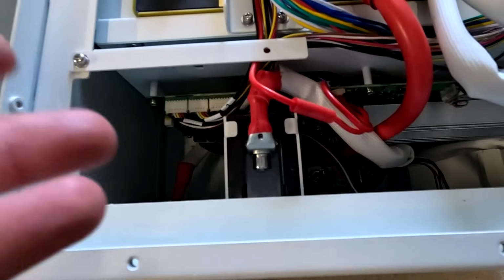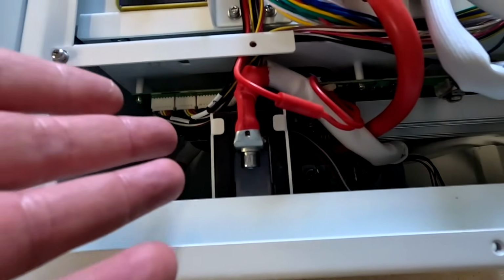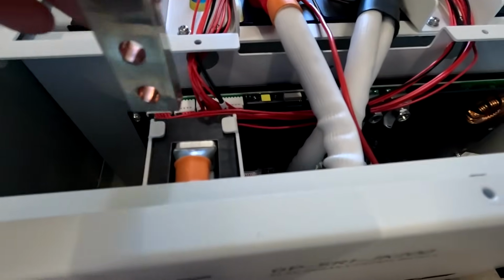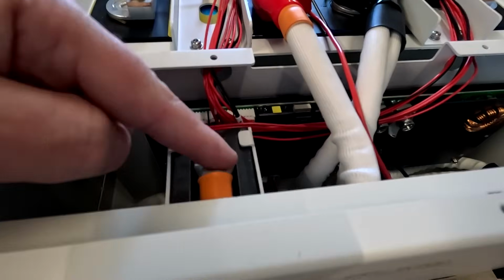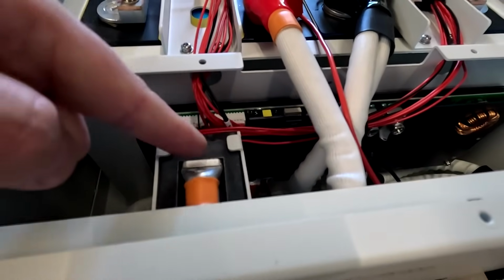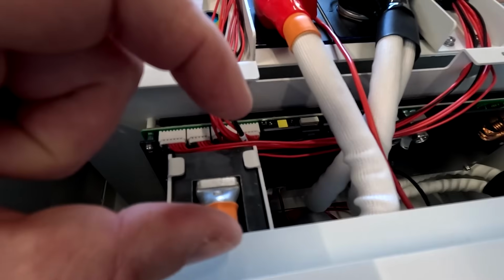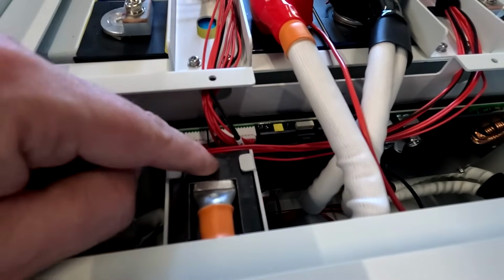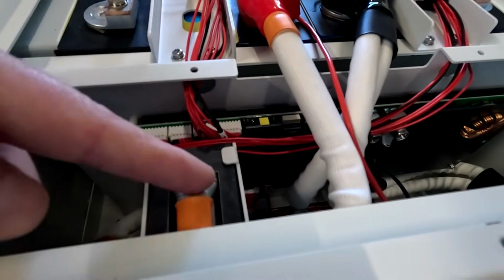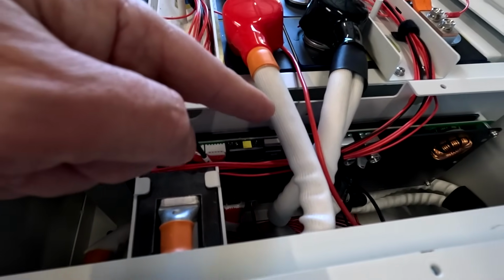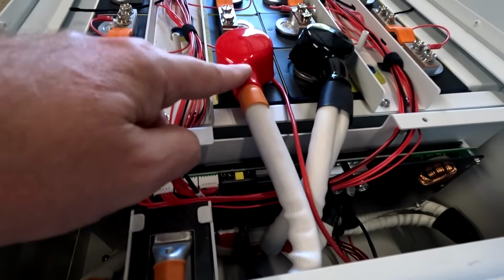But these ones here, I mean, we've got options, right? For example, you could have a piece of copper sticking here connected to the circuit breaker, and then connect your cable in a straight way directly to this copper bus bar. It's just a short piece and acts as a link between your circuit breaker and your cable. Then you can go off in a nice and smooth angle to your positive terminal of your battery.